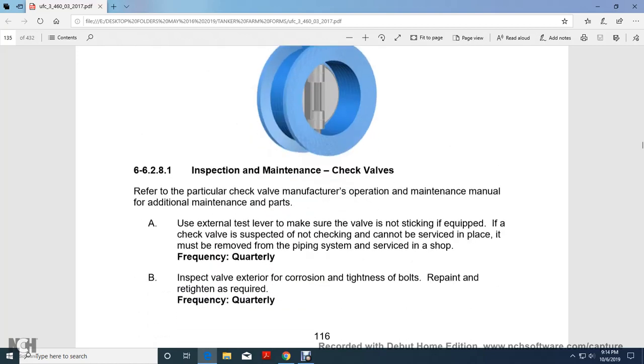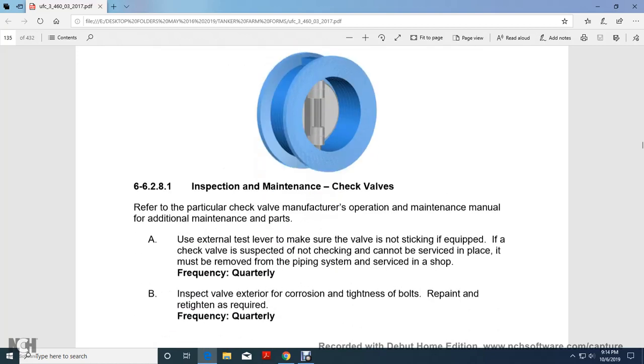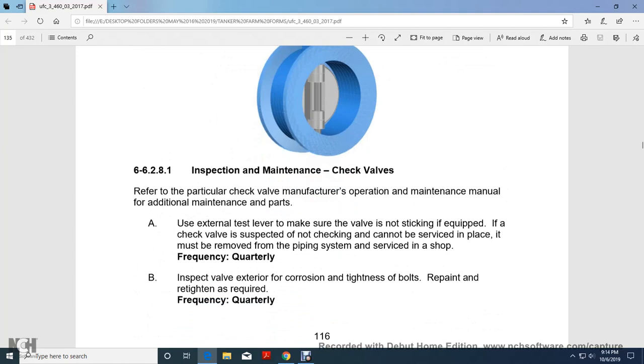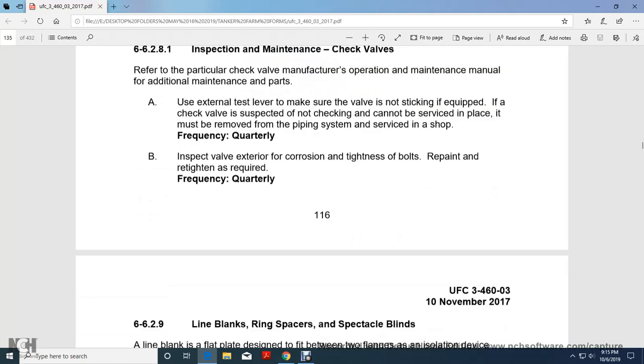This shows figure 6.7, the check valve inspection and maintenance. For check valves, refer to the manufacturer operation and maintenance manual for additional maintenance of the parts. For the external type, use the test lever to make sure the valve is not sticking. If a check valve is suspected of not checking and cannot be serviced in place, it must be removed from the piping system to the shop, and that frequency is quarterly. Inspect the valve exterior for corrosion and tightness of bolts, repaint and retighten quarterly.